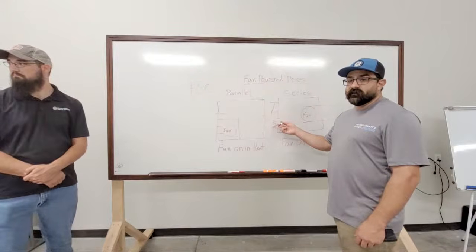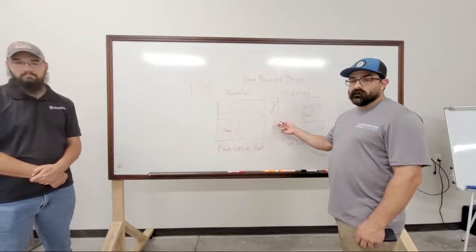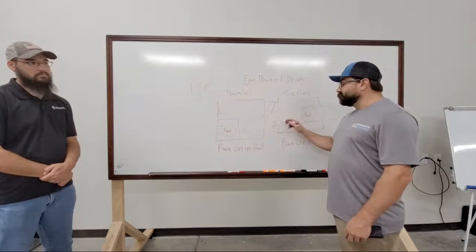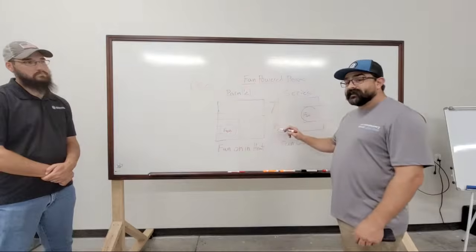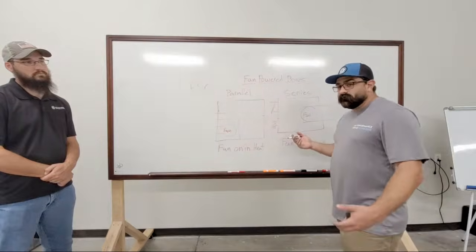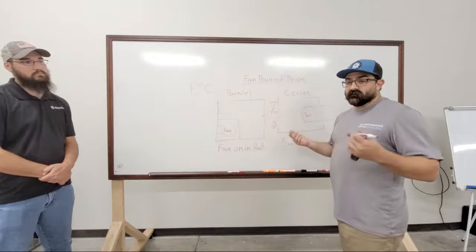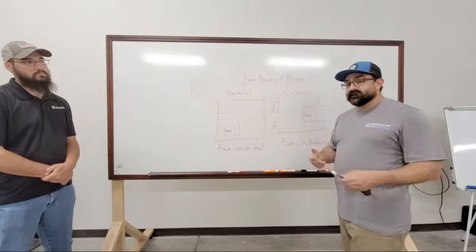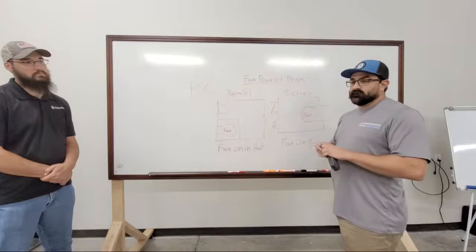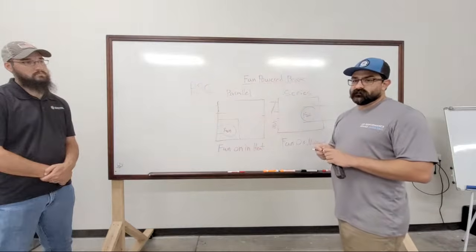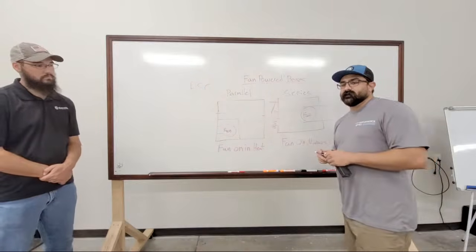By theory of design, you would not want one. I've seen some people that have put like return boots that had them. Why they did it, I don't know. I'm assuming they just slapped them up there trying to resolve an issue and didn't understand the cause of the issue. And that was one job a long time ago in Houston, and they ended up ripping them all out when we did the tenant improvement on the job.